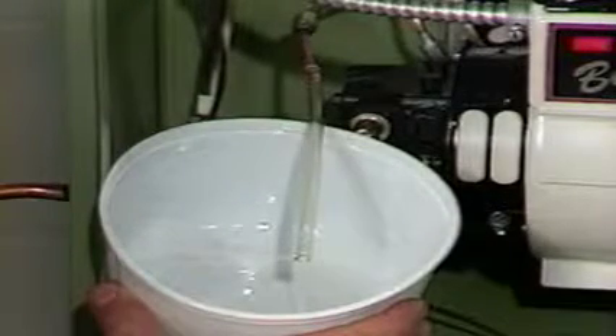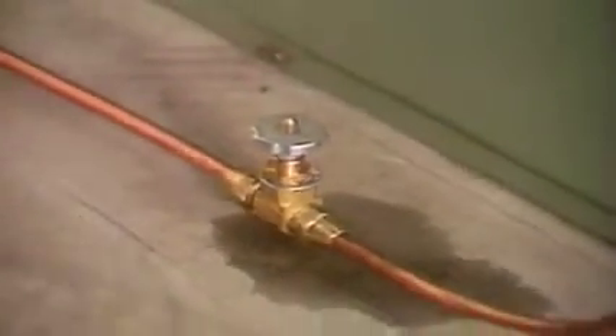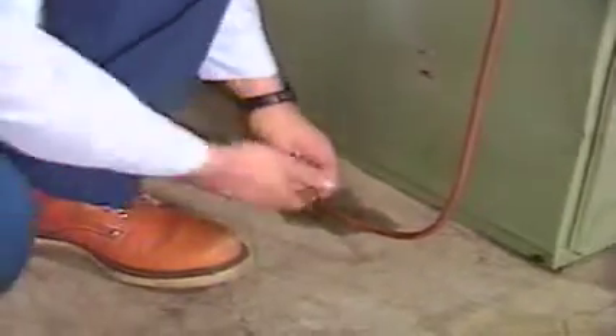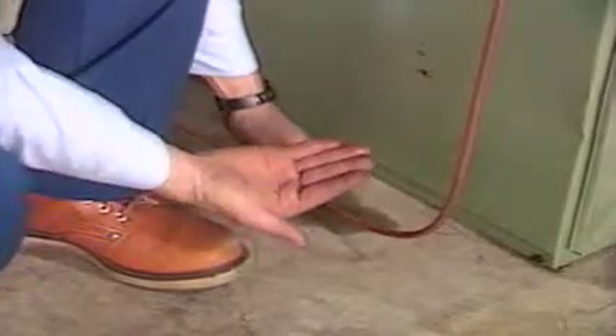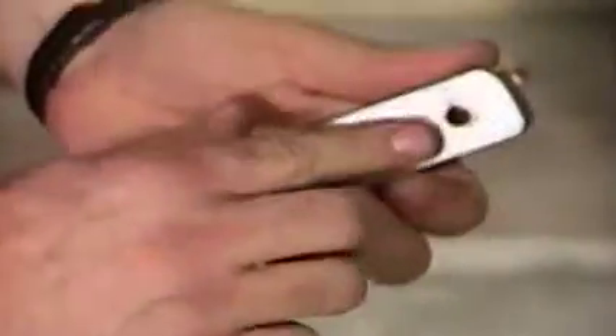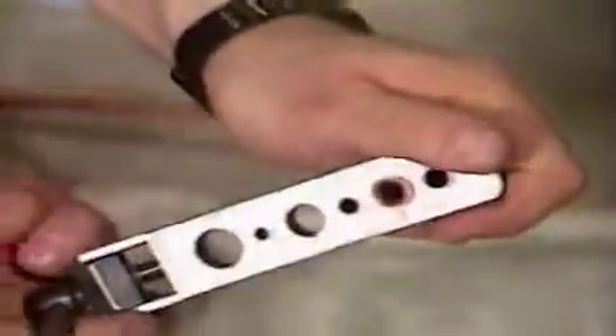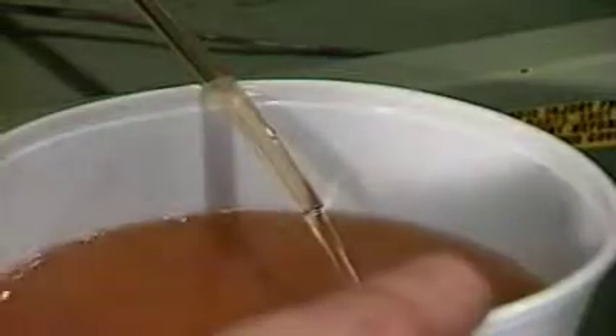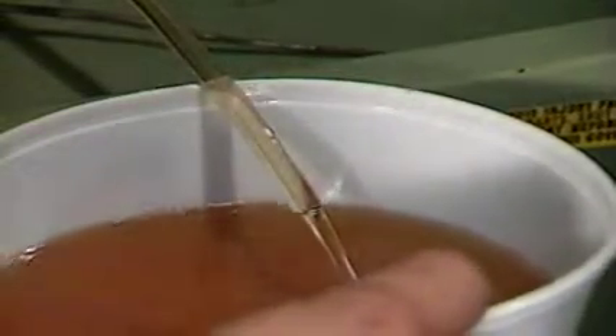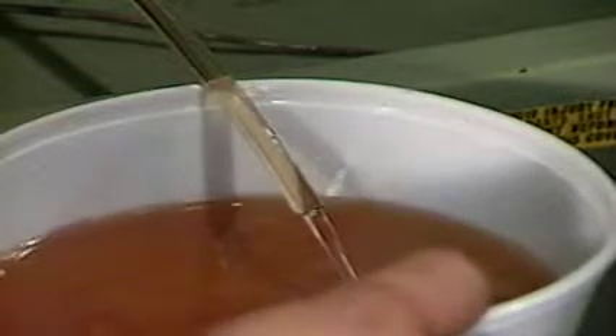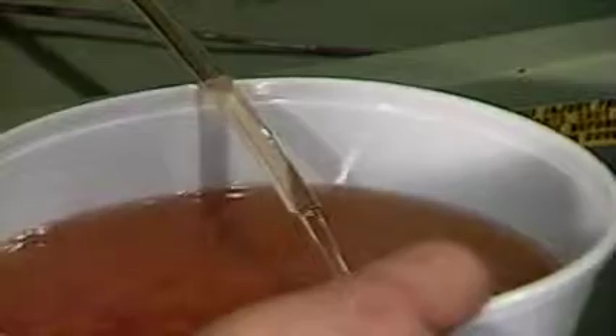Oil quality is the fourth condition you should observe at startup. Is there no oil delivery? Find the restriction, checking back along the supply line at each fitting to the supply tank, which you already know has oil in it. And here's the problem, quickly solved by reflaring the supply tubing using the tools in the toolbox. In just minutes, the tubing carries a new flare, and the supply line is ready to be joined again, this time without the leak. Is the oil white or frothy? Bleed the pump. Only when the oil is clear and air-free can you consider the problem solved.